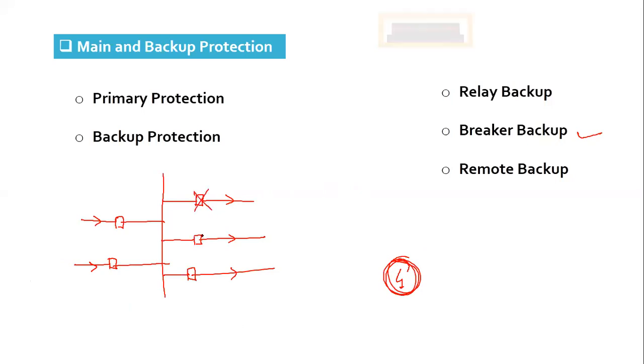And suppose the primary relay fails to operate, then what do we do? We trip all the breakers associated with that bus bar as a backup protection. So that is what is called breaker backup - all the breakers associated with a bus bar at a substation are tripped following the failure of a protective scheme in the downstream part of the power system.